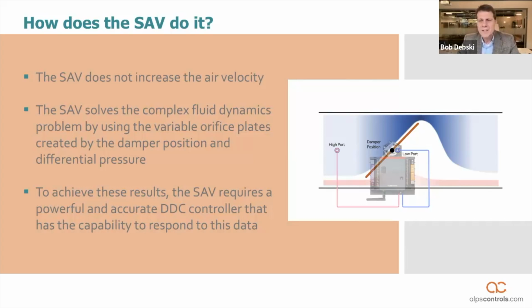The only way this can be accomplished is by building intelligence into the smart air valve. And this has a major impact on the opportunity for you, because in order to pull off this level of mathematics, the DDC controller must be installed. That patented technology resides within the VAV controller.